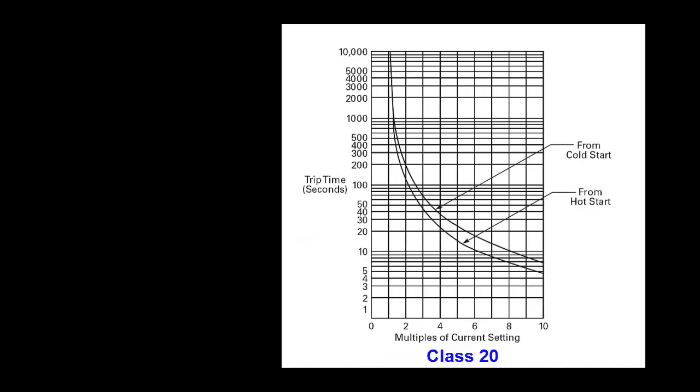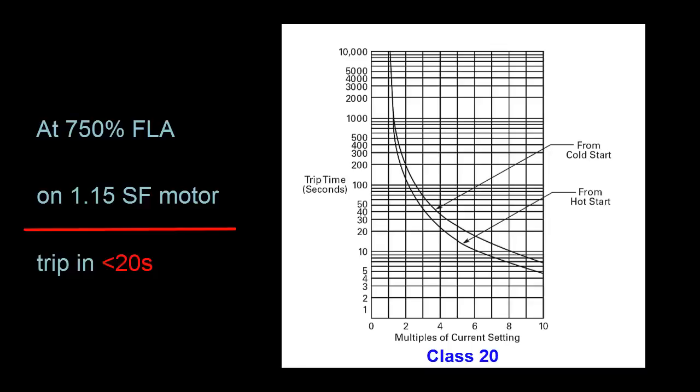This one I'm looking at now happens to be a trip class of 20. A trip class of 20 means that at a constant current that is 750% of the FLA current setting on a 1.15 service factor motor, the motor will not take more than 20 seconds to trip.